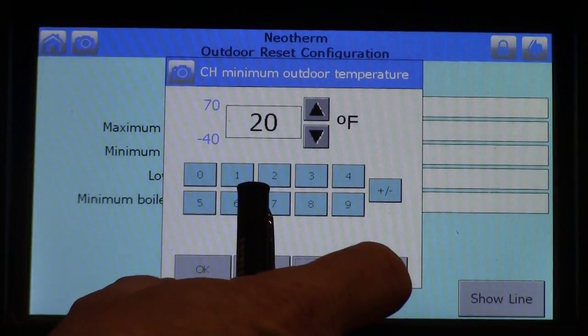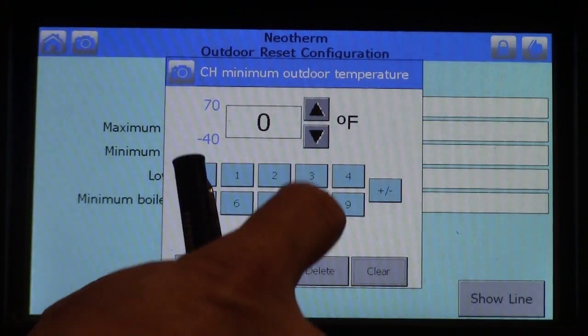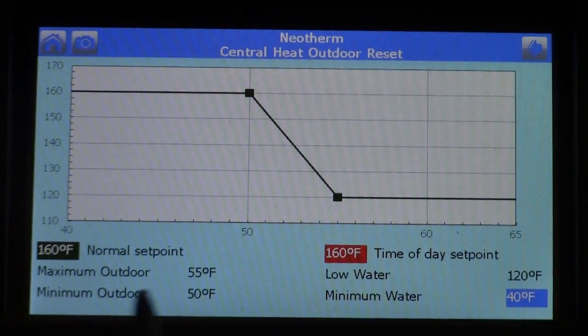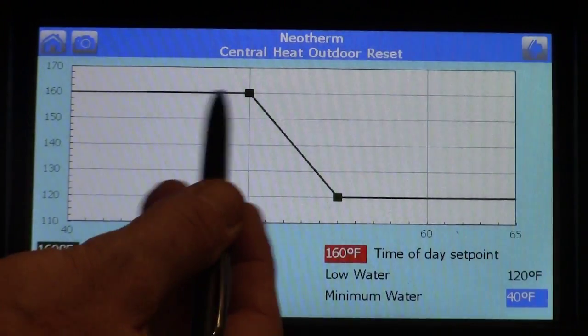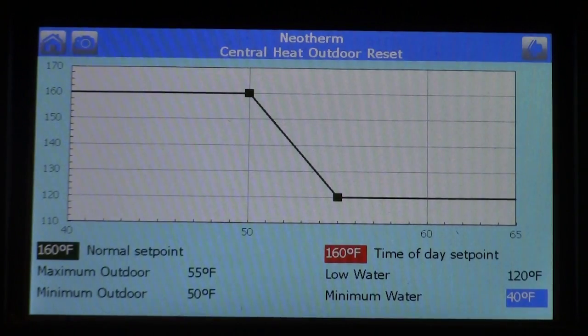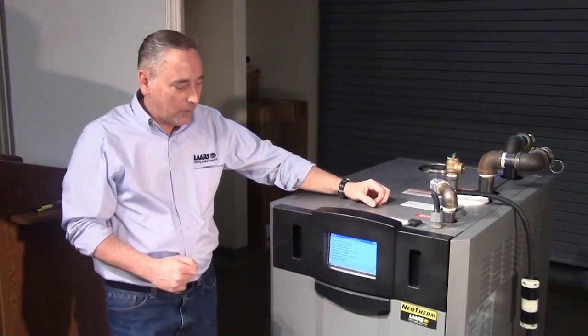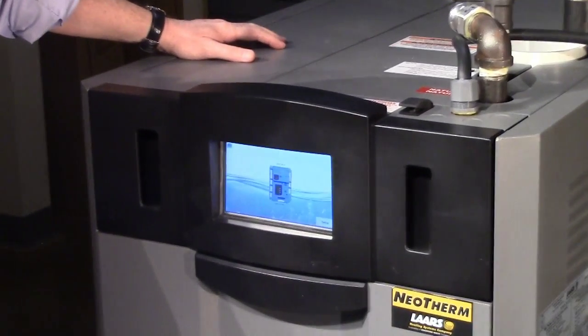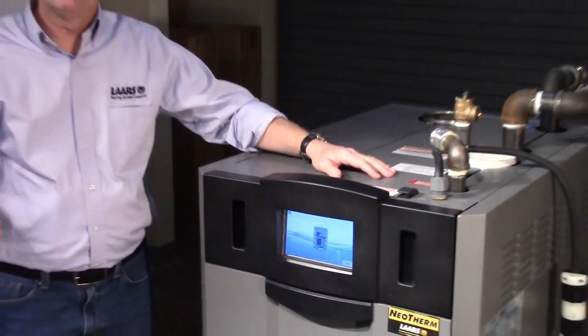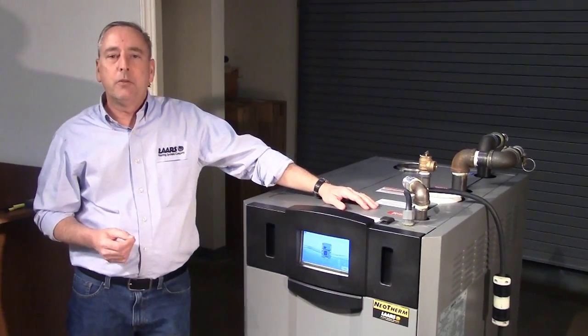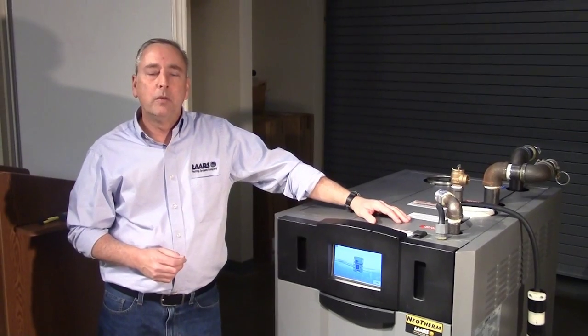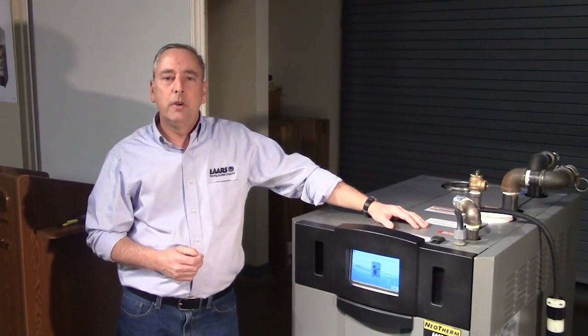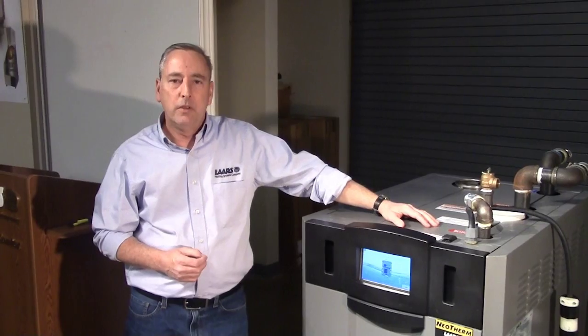I'll also change the max outdoor temperature to 50 degrees for this example. Go back to show line and now you can see your updated curve. If you don't like the set points, click the back arrow, come back in, and set it up differently. That's it — very simple. From there we're going to go back to the home screen. If you have any technical questions, please contact the factory and ask for product support. That number is 1-800-900-9276. Thank you.